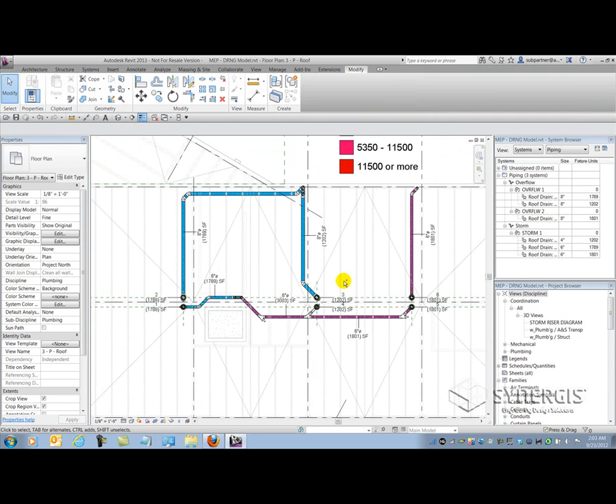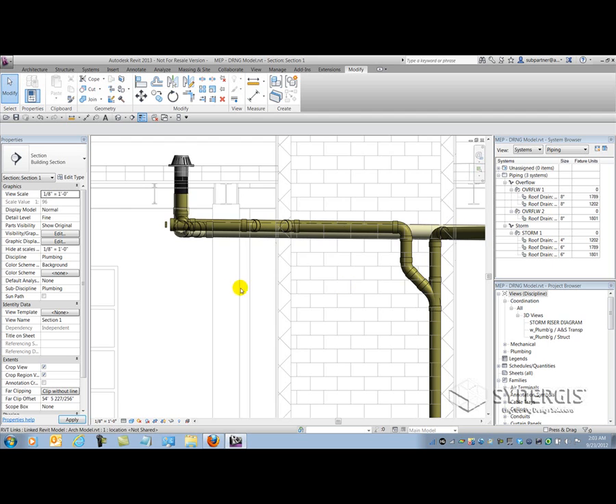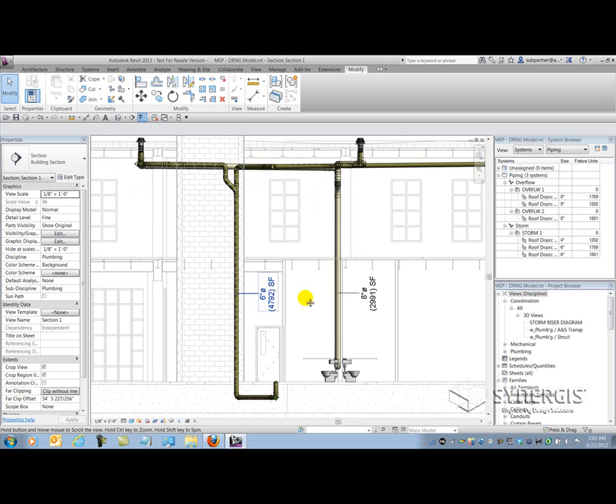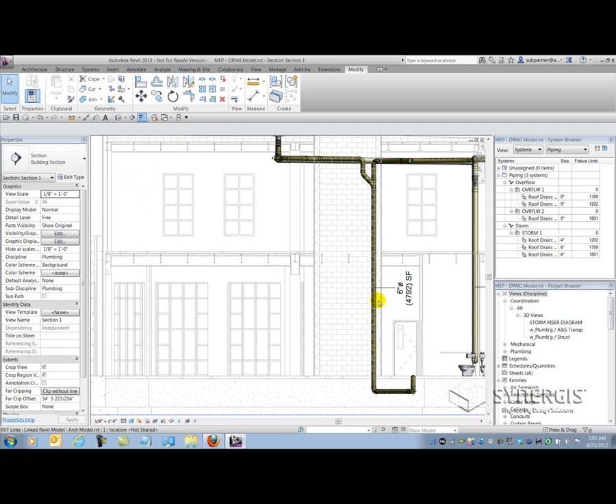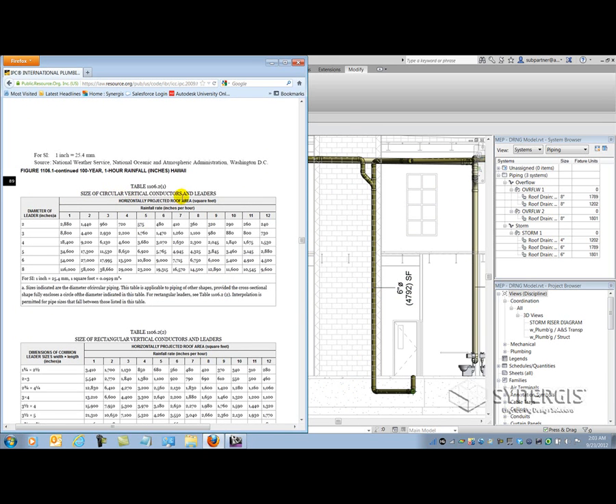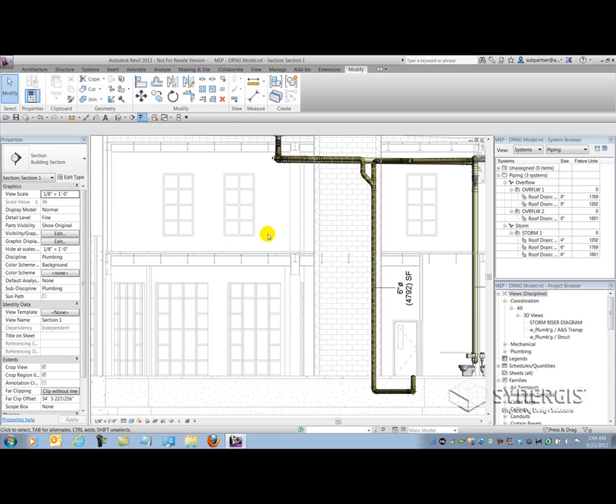Now I can also look at the vertical leaders, or conductors. Swinging through my views, here I've got my vertical conductors. I'll refer back to the code to see what's the best size pipe to use. Is 6 inch sufficient? Going back to the code — again in the 4 inch rainfall range — I come up to the size of circular vertical conductors and leaders, look at 4 inches, and check the coverage. 4792 square feet puts me up into the 8650 range, which means 5 inch pipe. But again, I'm not going to use 5 inch pipe, so I'll use 6. And I can see that I'm in code. I've basically covered everything I could using the available tools to make the best informed decision on how to size my pipe network.